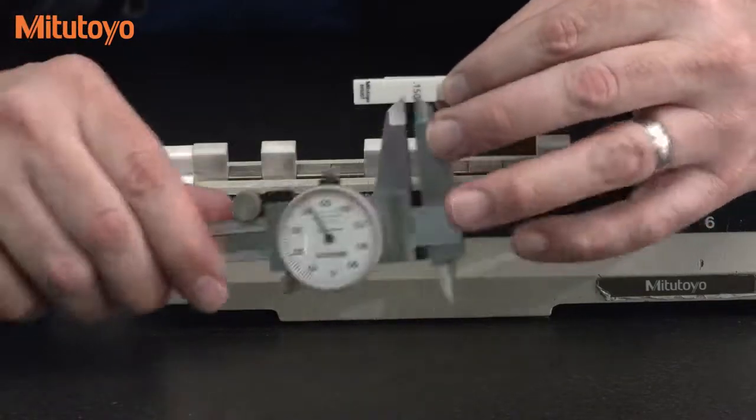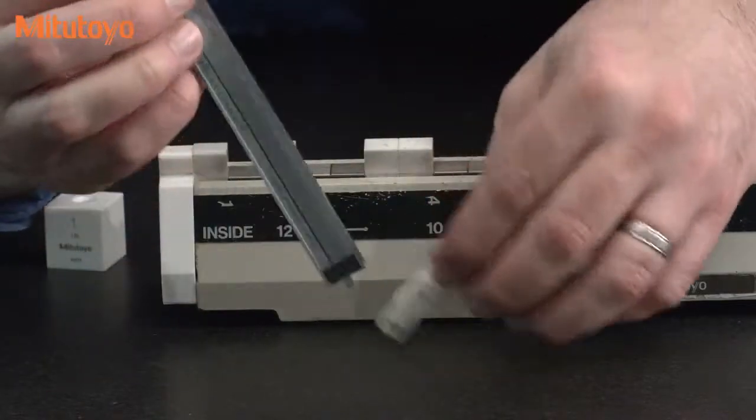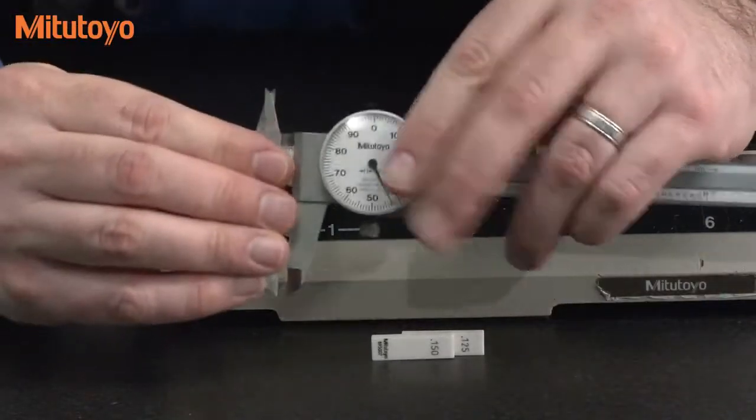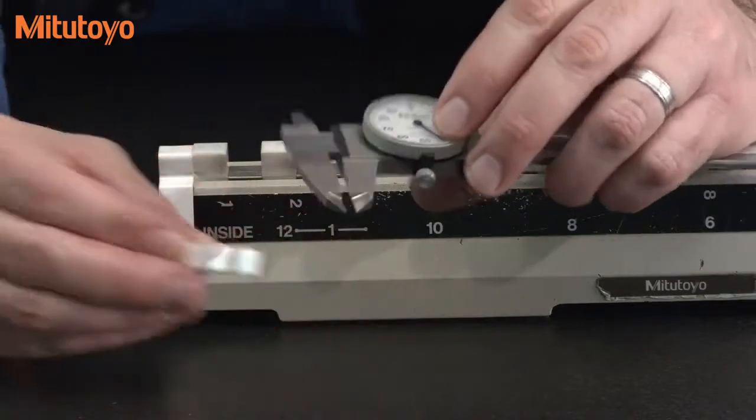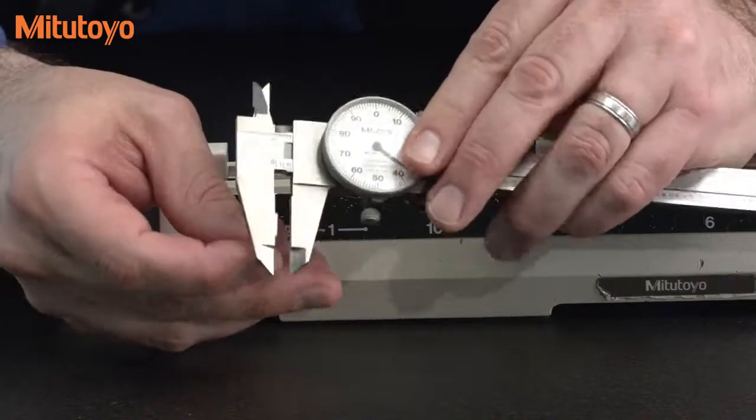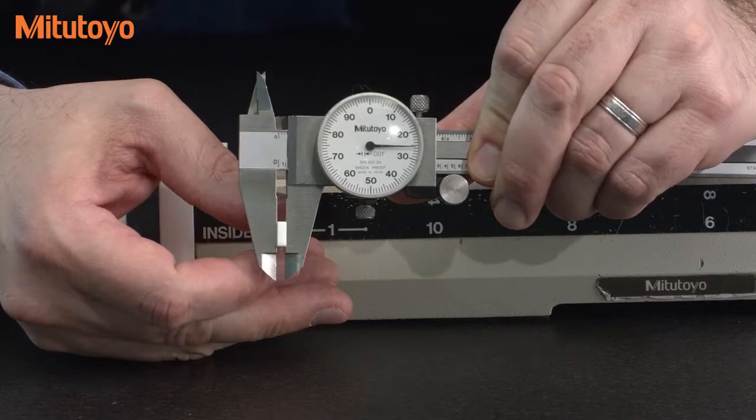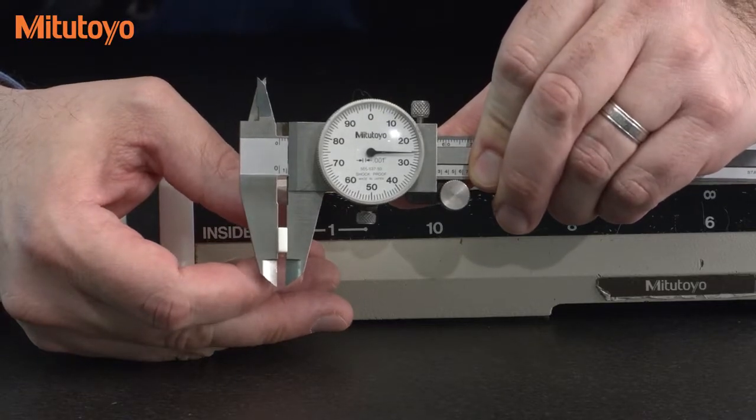For this style caliper, this inch size caliper, with the .125 block if I was to measure that, I should be at the 3 o'clock position like you see here.